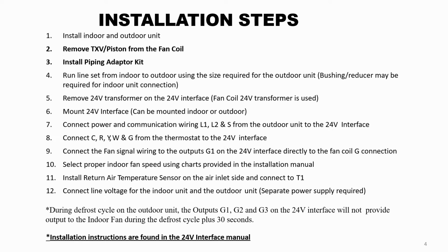One note about the G1 output on the 24-volt interface is that during the defrost cycle on the outdoor unit, the outputs G1, G2, and G3 on the 24-volt interface will not provide output to the indoor fan during the defrost cycle plus 30 seconds. That's why we're using the G1 output going directly to the fan coil from the interface kit as opposed to using the G signal from the thermostat, so that we can turn the fan off when the unit goes into defrost to prevent blowing cold air on the occupants.